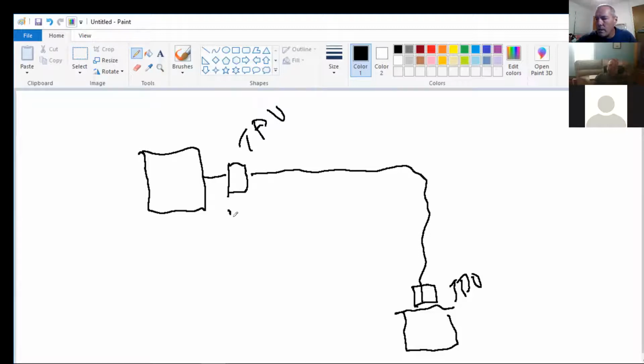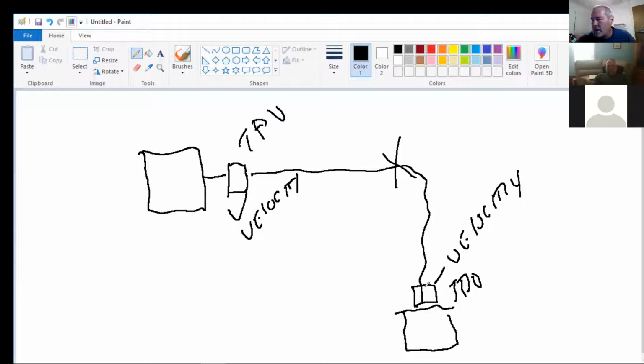On this one we record the velocity, and on this one we record the velocity and time of the fault, and that information goes back to the Energy Control Center via SCADA. They can get it down to about 75 to 100 feet—they'll be able to tell you where the fault's at, location-wise. That's pretty cool. It is pretty cool, and I can tell you it's extremely helpful.